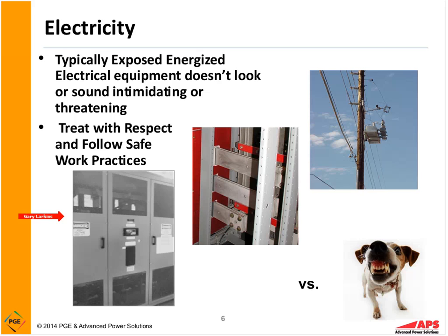Now, in the lower left-hand corner, we're talking about that unit substation, that transformer. The risk is probably very low that something's going to occur right when someone's maybe walking past. But in many electrical rooms on construction sites or remodels, we'll find that maybe a contractor puts their print table there or the break room, or we'll find folks going into the electrical room to make that their break room. So what am I doing to the probability of the risk of injury when I'm having somebody stand or sit in front of that gear for a half hour, maybe an hour at a time? It goes way up. So what is your policy around allowing folks into electrical areas where we have the potential exposure?